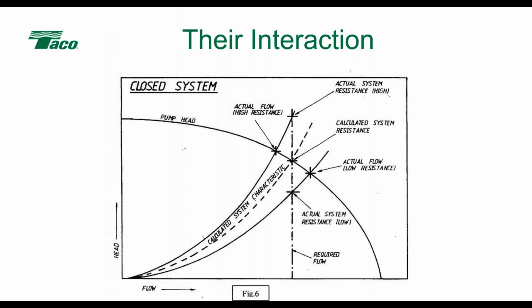So if I look at a pump curve, forgetting all the set point pressures, what we have to understand is that we, as engineers, design a system for a given flow and head. The reality is that the actual system head is usually never what the design head is. It's higher or lower. As it moves higher or lower, the system flow rate is going to move across the pump curve to that higher or lower flow rate. It has to, because it has to follow that curve. And that's part of why we put VFDs on, because we can trim that down to exactly where we need it to be.